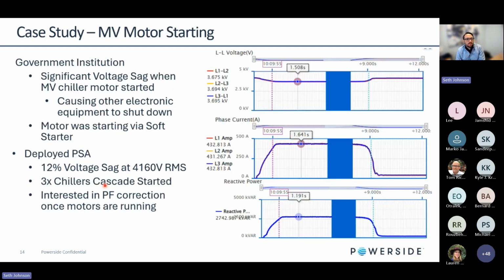And then the last case study I'd like to go over here is a medium voltage case study. So I stated earlier that we do power system analysis for both low voltage and medium voltage applications. And this was a 5 kV class application for a government institution. They had reached out to us because they had a significant voltage sag when some of their medium voltage chiller motors started. Now, these motors were on soft starters, okay? So they were limited to, let's say, 300% max load at inrush, but they were still experiencing a significant voltage drop. And it was causing other electronic equipment to shut down, particularly some VFDs and other power electronics in the facility.